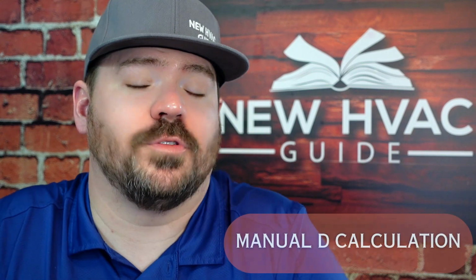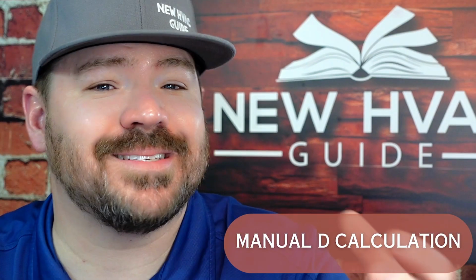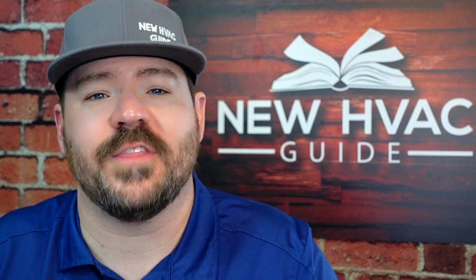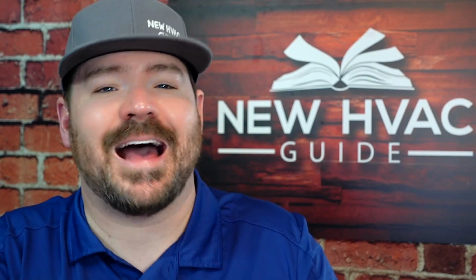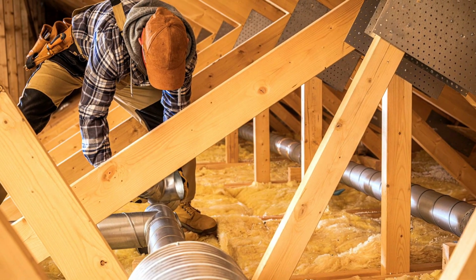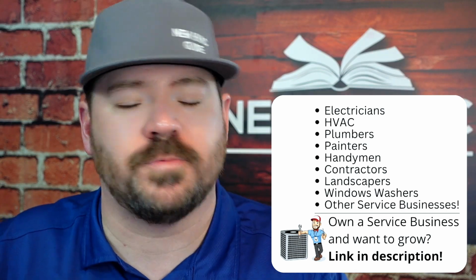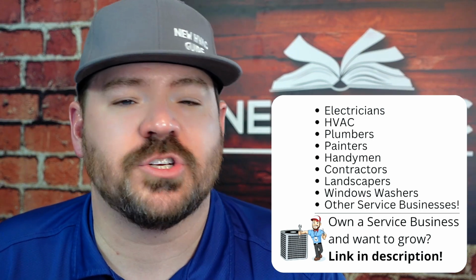Next, let's talk about a Manual D calculation. So you've decided what size that system needs to be, you've narrowed it down, and now you're looking at installing the system. You've got a pro in there installing the ductwork. This calculation is overlooked more than load calculations when it comes to rules of thumb a lot of guys use in our industry. You can have a perfectly sized system, but if that ductwork isn't installed properly, you can have a whole array of issues. In fact, aside from questions on brands, I probably get more questions on my YouTube channel about one room being hot or cold, or certain parts of the house not heating and cooling like it should — all because in most cases we're talking about ductwork issues.